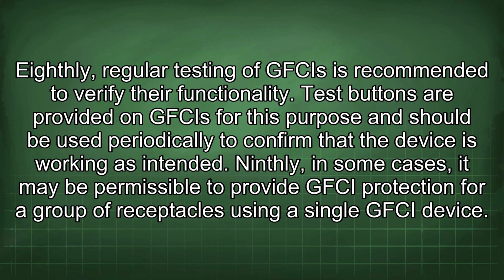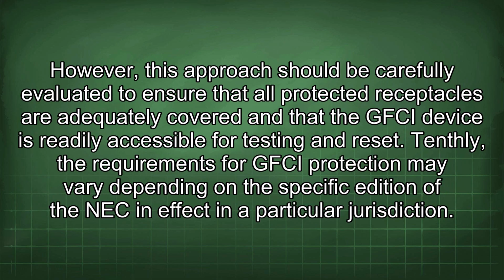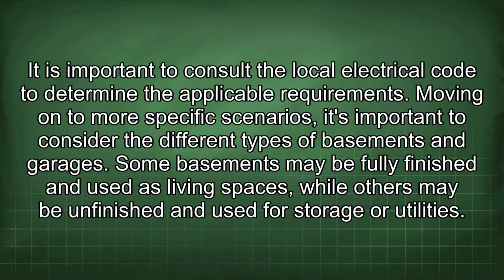working as intended. Ninthly, in some cases, it may be permissible to provide GFCI protection for a group of receptacles using a single GFCI device. However, this approach should be carefully evaluated to ensure that all protected receptacles are adequately covered and that the GFCI device is readily accessible for testing and reset. Tenthly, the requirements for GFCI protection may vary depending on the specific edition of the NEC in effect in a particular jurisdiction. It is important to consult the local electrical code to determine the applicable requirements.